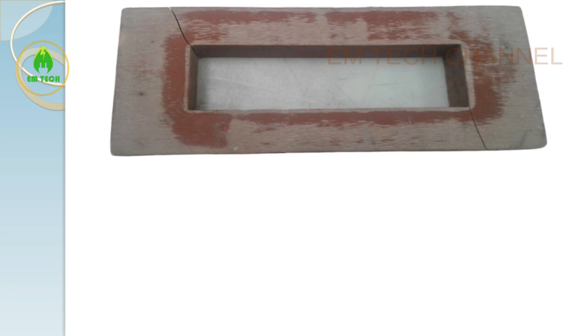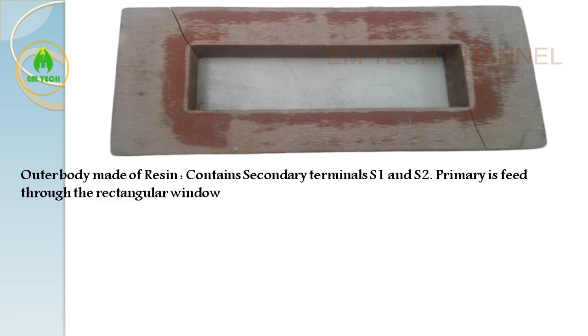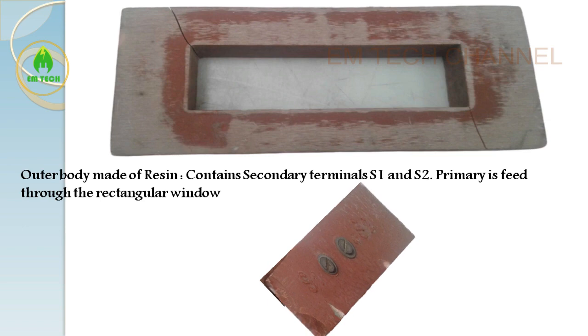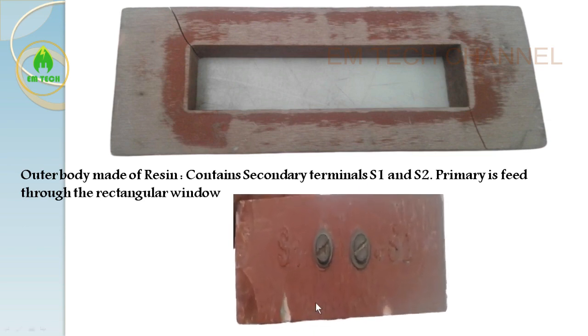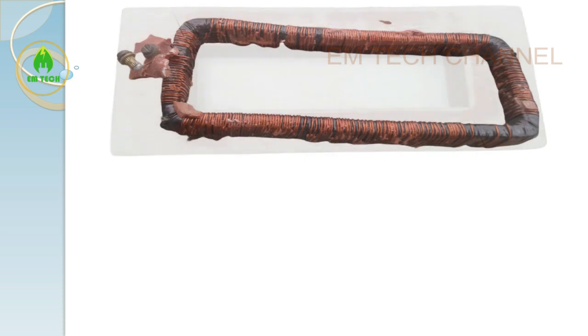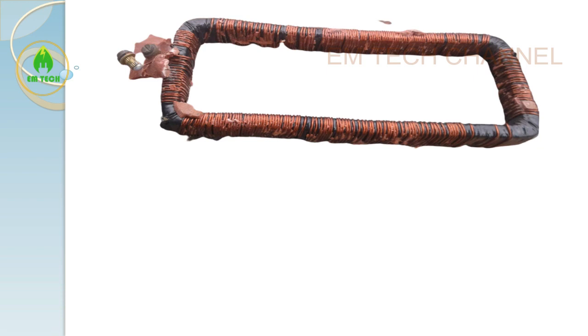The two terminals above are the secondary winding — in this type, only the secondary winding is physically present; the primary winding is not present. The window or hole for the cable or bus bar acts as the primary. This current transformer is a toroidal or window type of rectangular shape. This is the outermost shell visible externally. It has terminals S1 and S2 — in this view they are not directly visible but they look like this: S1 and S2.